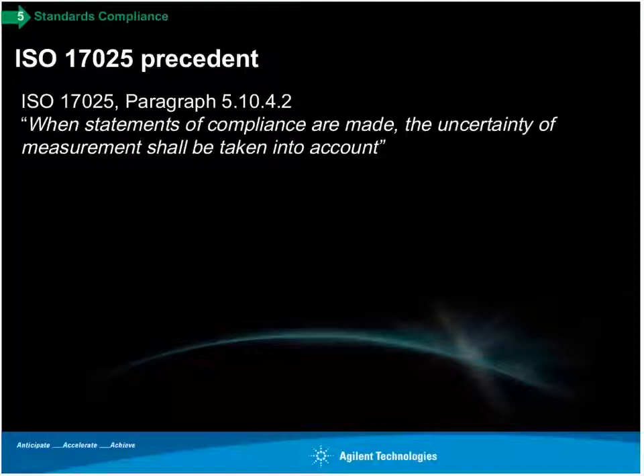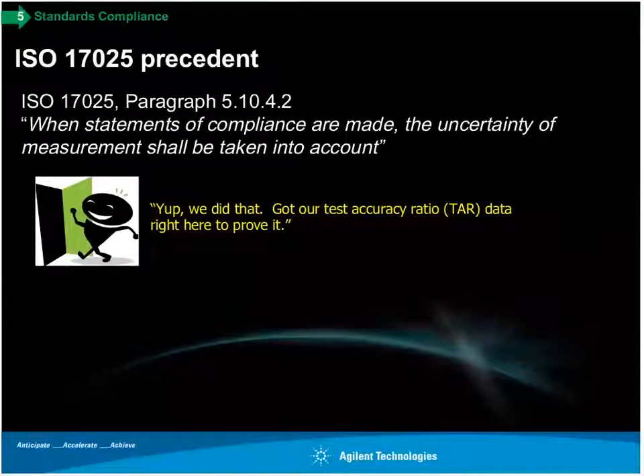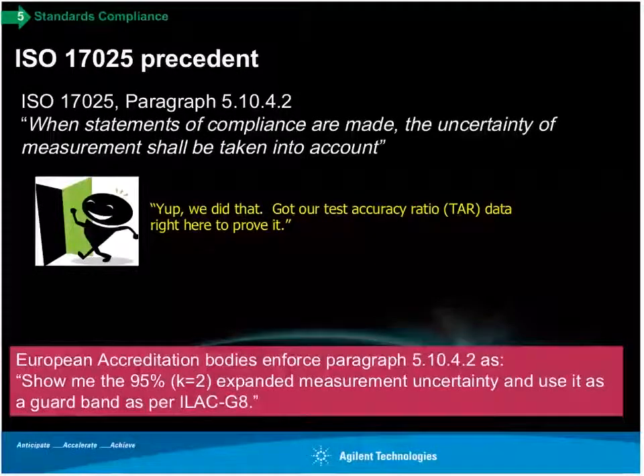One of the key statements in 17025 is that when statements of compliance are made, the uncertainty of measurement shall be taken into account. This one causes unbelievable amounts of discussion within the metrology community. You can see everything from some labs saying, yep, we did that, we got our test accuracy ratio right here to prove it, we're out of here. Well, test accuracy ratio is not the same as measurement uncertainty. So when the accreditation body is reviewing a laboratory, they're not going to allow that. But if they don't look, sometimes that gets used.